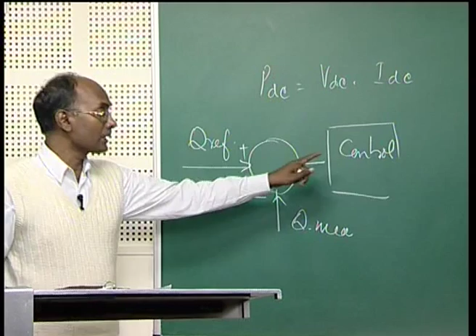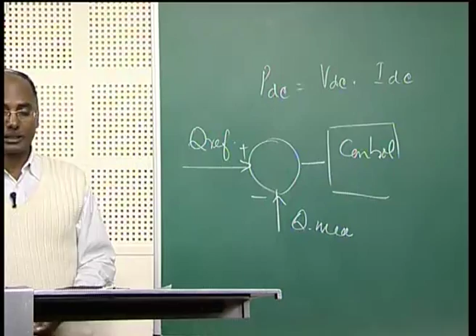The outputs of the active and reactive power control loops are the input to the pulse width modulated pulse generator. Similarly we can go for the real power, and these two inputs are given to the pulse width modulated pulse generator, which generates the firing angle for the converter as well as the inverter, because we are controlling the real power and reactive power. This input is given to the pulse width modulated control of your rectifier. The PLL provides the synchronous signal for the pulse generator. The pulse width modulated pulse generator sends the pulse signal to drive the valves, or IGBTs, in the converters, and thereby we can control the quantities accordingly.